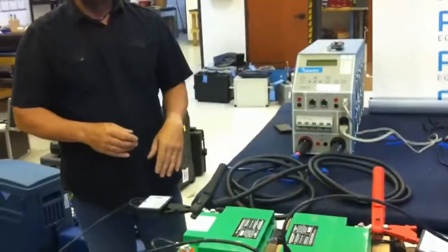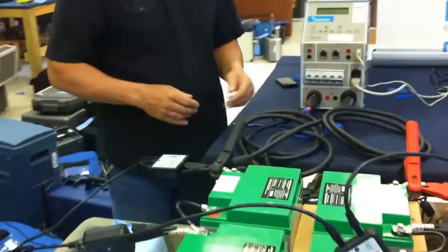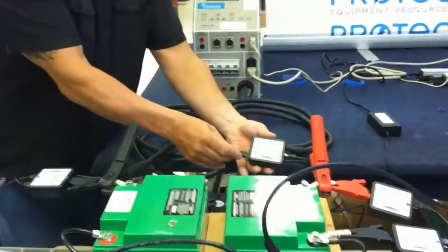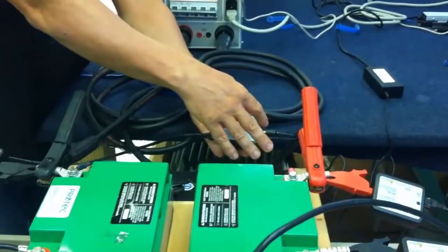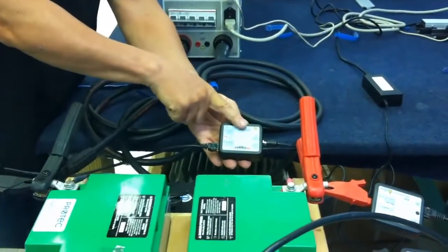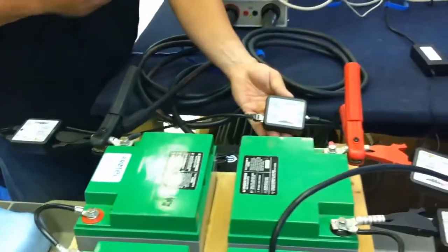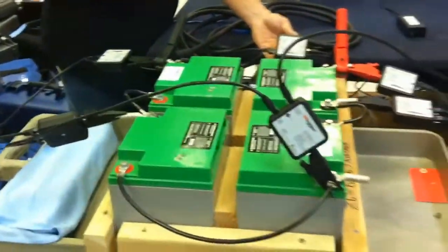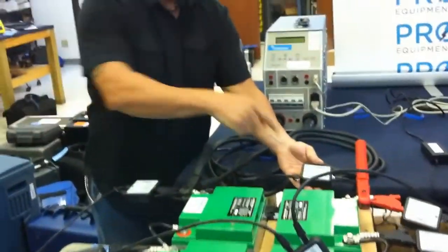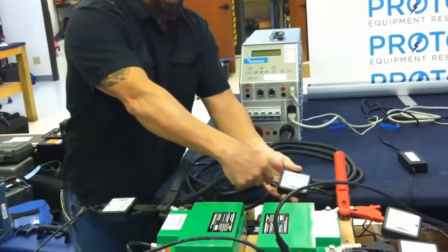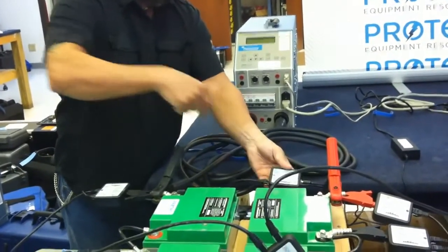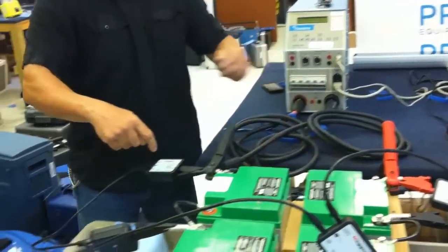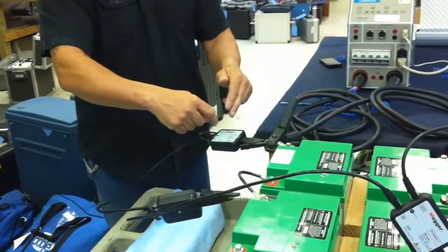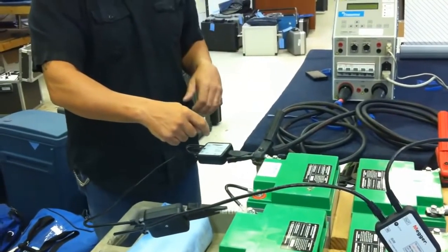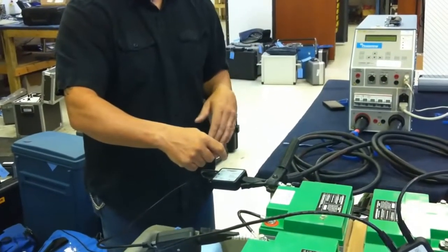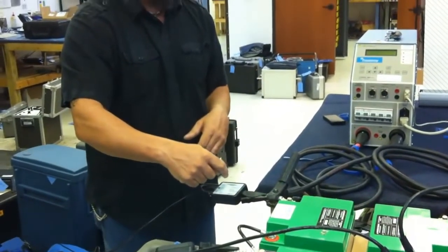Now, the battery voltage monitors: we connected the master module where we provide DC input power to it, which energizes each of the battery voltage monitors connected onto each of our jars. We connect using our first patch cord to the very first battery voltage monitor, which is connected to the negative terminal of the first, or last jar in the string.